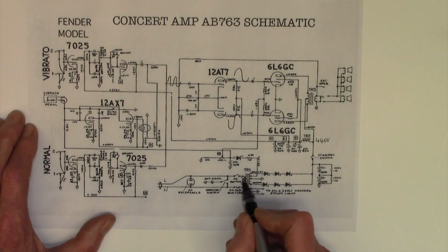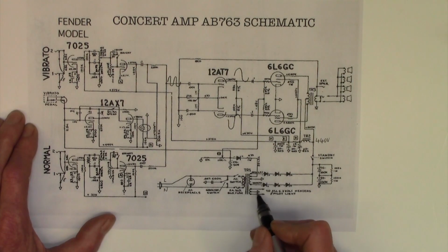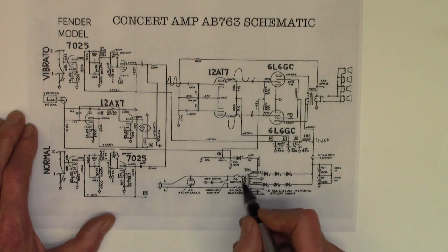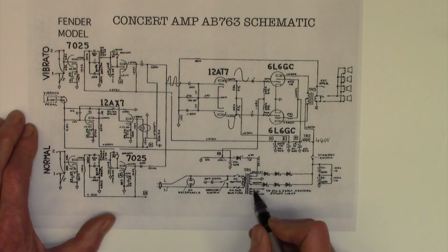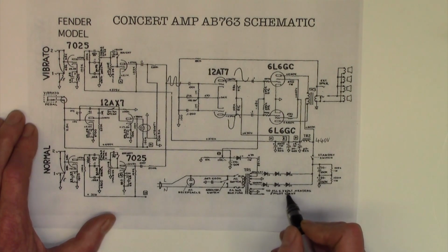So if you had 240 volts in and you want 6.3 volts out, which we do here - here's our 6 volt winding - you'd have maybe a 40 to 1 turns ratio. So for every 40 turns on the primary, there'd be 1 turn on the secondary to get that voltage.